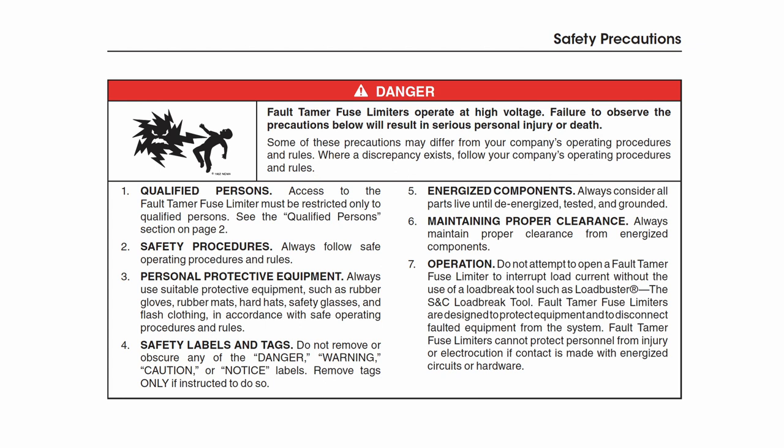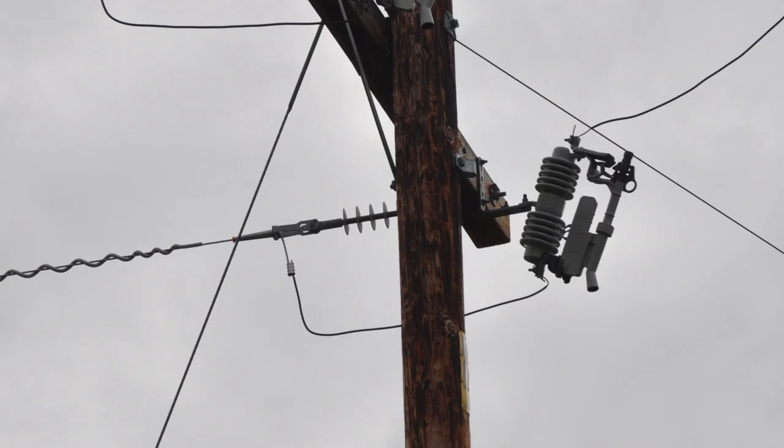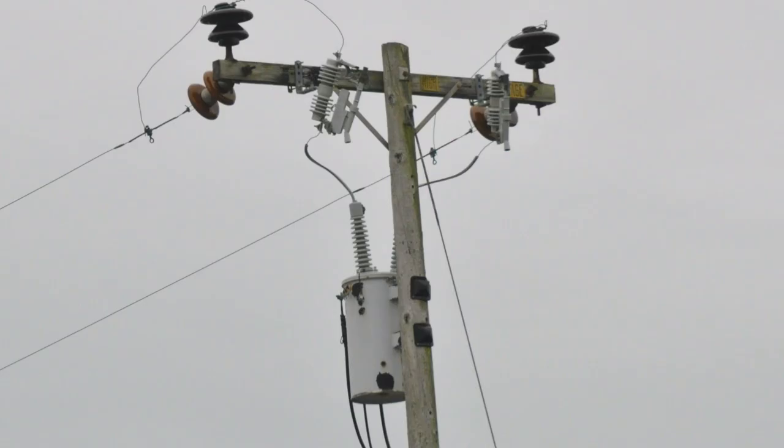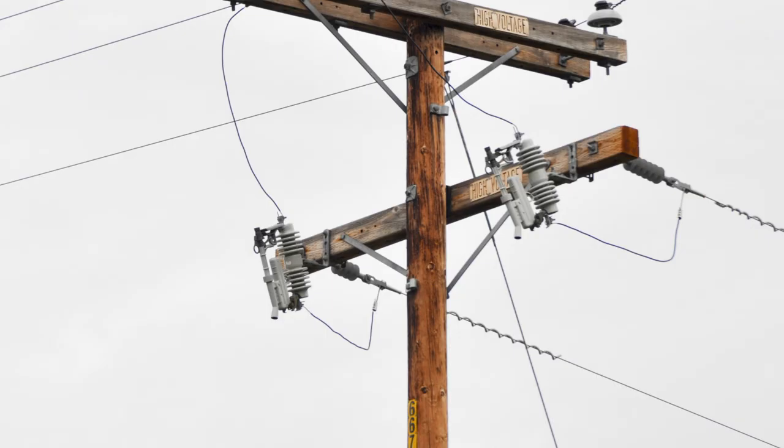Some of these precautions may differ from your company's operating procedures and rules. Where a discrepancy exists, follow your company's operating procedures and rules. Fault Tamer Fuse Limiters combines the functionality of a conventional expulsion fuse cutout and a backup current limiting fuse in one powerful, easy-to-install package for the protection of new or existing overhead pole-top transformers through 25 kilovolts. This video will demonstrate fusing and installation of a Fault Tamer Fuse Limiter into a Type XS fuse cutout mounting.